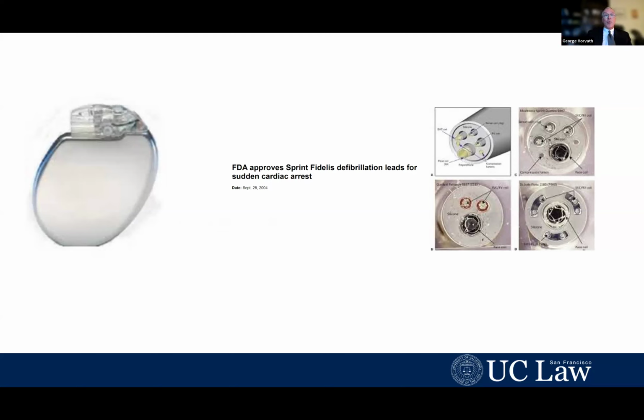In 2004, the FDA approved a new lead shown here called the Sprint Fidelis. This lead was much narrower, had a much smaller diameter than earlier leads. We thought that meant it was less likely to block off veins. Its low profile, its softness made it less likely, we believe, to perforate the heart, which was always a risk.